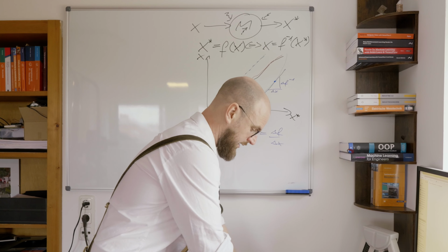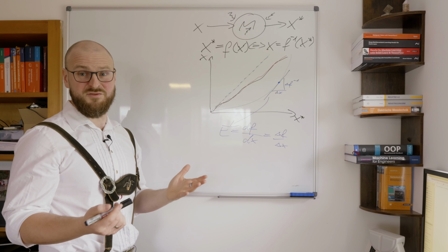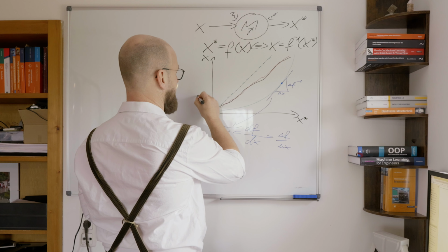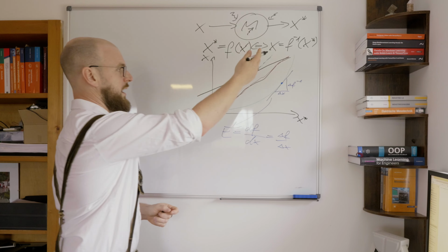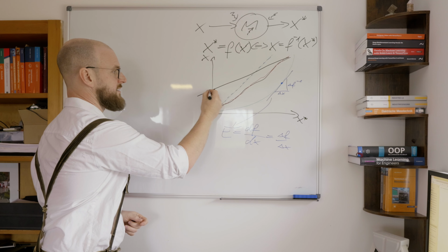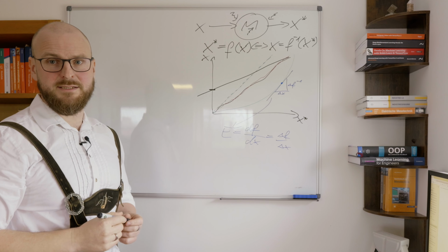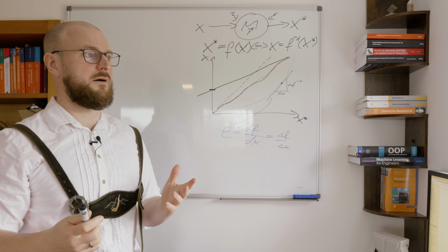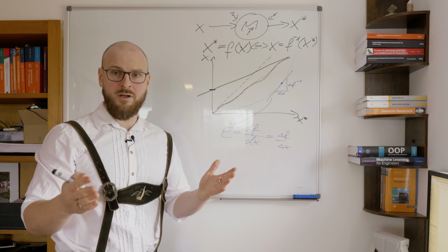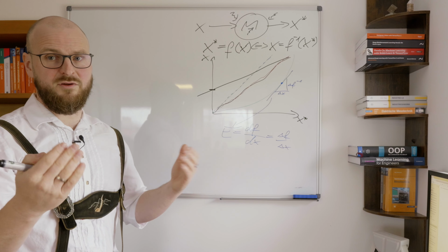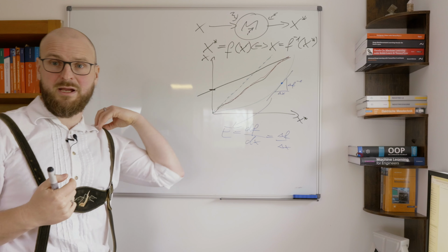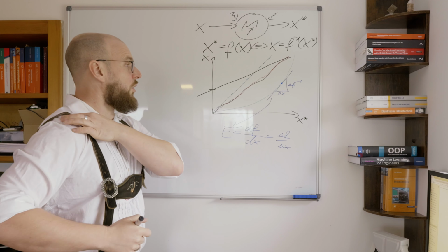One important thing which is useful in practical usage is a live zero point, meaning we have a curve like the black one over here which hits the y-axis above 0. What does that mean? Think of a light barrier. When you cross it, it will give you a value, and now if you define those values which are sent by the light barrier that way, that you always get a value.